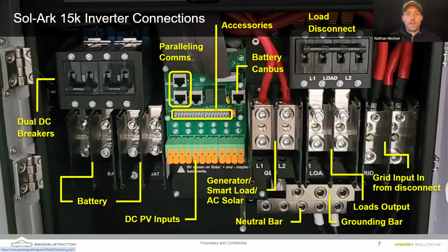In the center of this picture, you can see the comms board for the Sol-Ark, as well as what's at the bottom of the green and orange there, Daniel? The MPPT inputs? Yeah, those are MPPT inputs. We're looking at 3 independent MPPTs. That's our maximum power point tracking devices. That's to bring in your DC coupled solar. And then we have the accessories bar in the center. We'll talk about some of those pins.